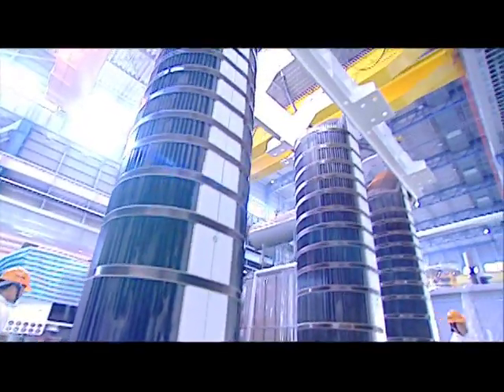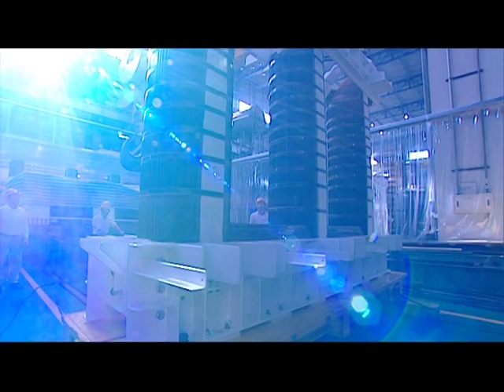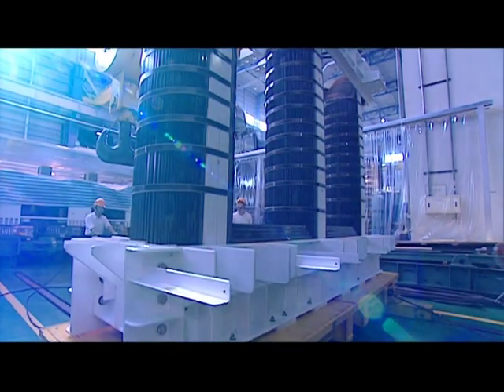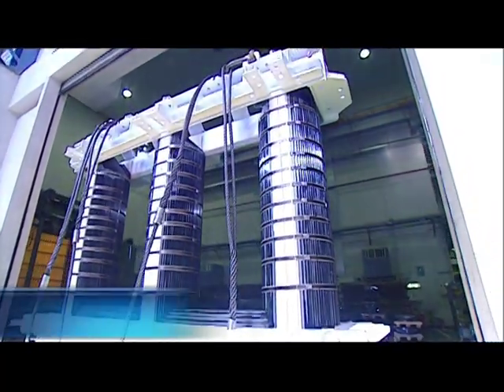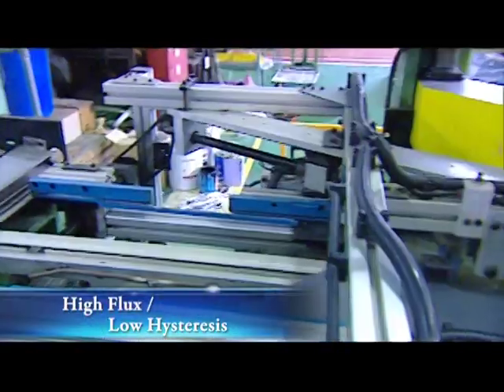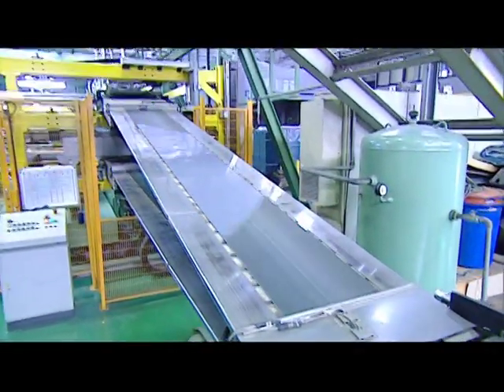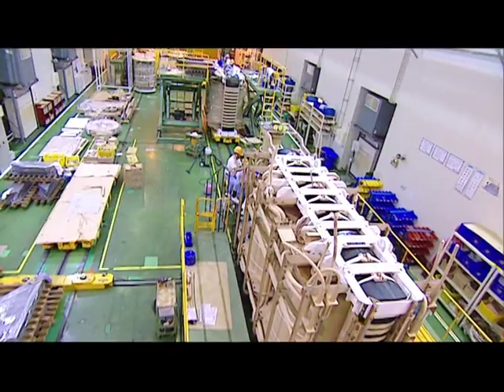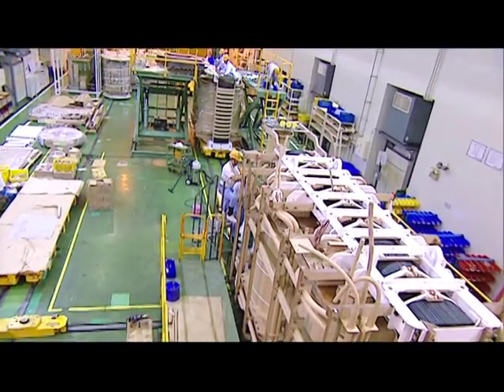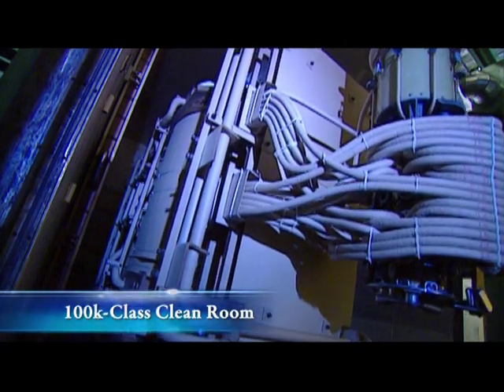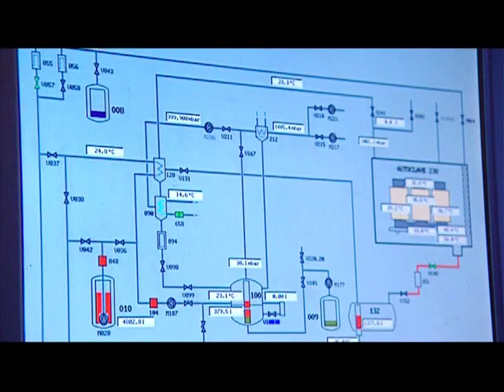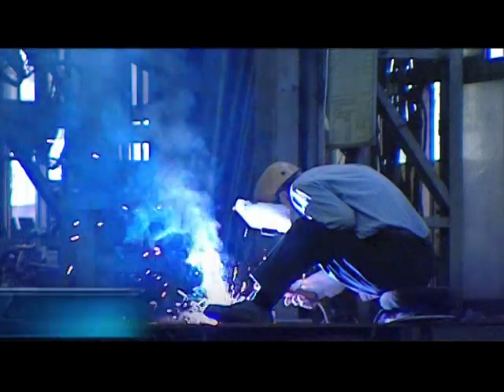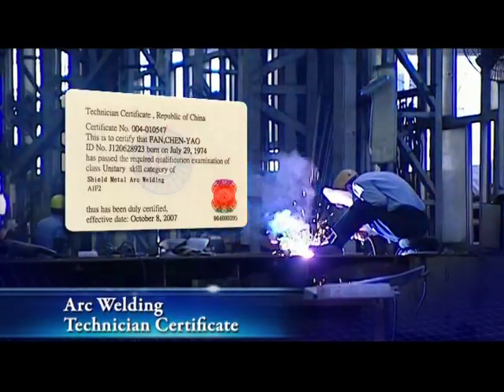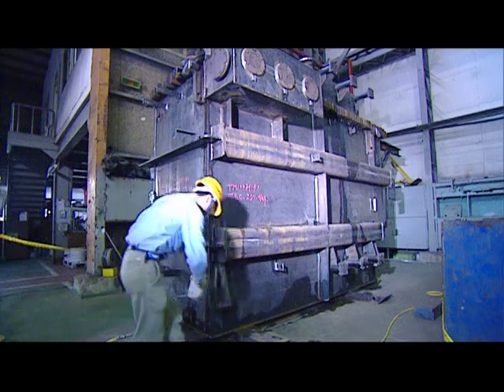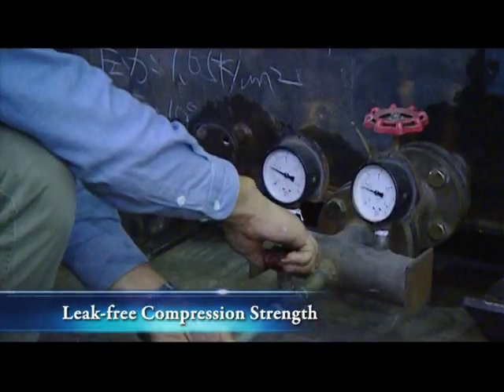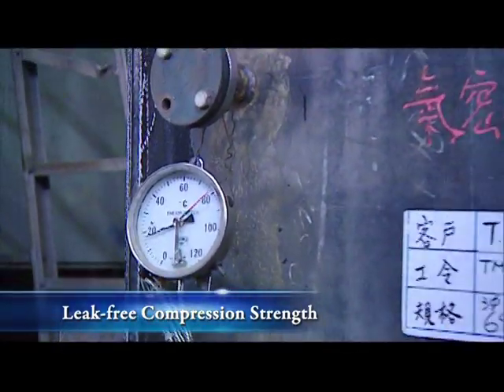Transformer production encompasses careful selection of raw materials, receipt inspection procedures, insulation material processing, the use of high flux, low hysteresis loss silicon steel, copper coil winding, and core cutting, stacking, and assembly. All internal assembly procedures are performed inside 100K class cleanrooms, controlled for particulates, humidity, and temperature. Certified welders assemble tanks and relevant components. Semi-finished tanks are subject to leakage tests that ensure they are leak-free and meet compression strength requirements.